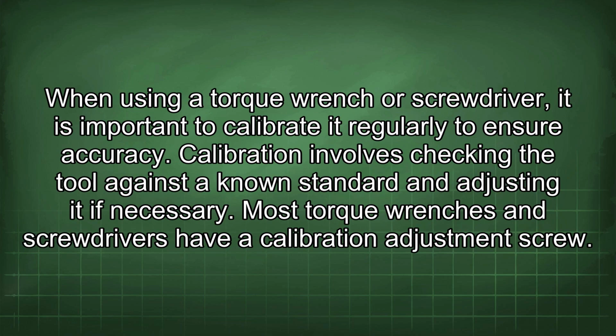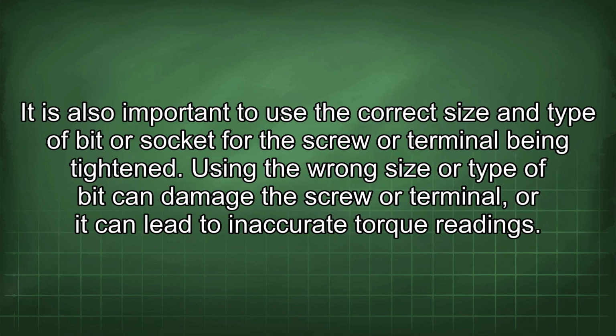When using a torque wrench or screwdriver, it is important to calibrate it regularly to ensure accuracy. Calibration involves checking the tool against a known standard and adjusting it if necessary. Most torque wrenches and screwdrivers have a calibration adjustment screw.